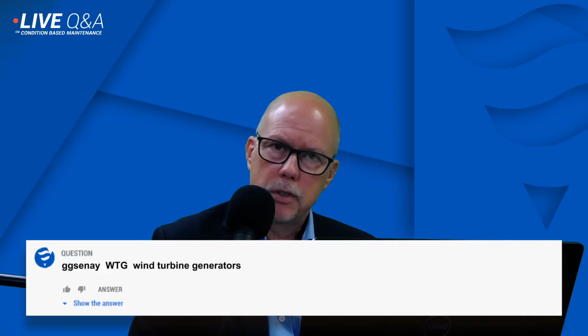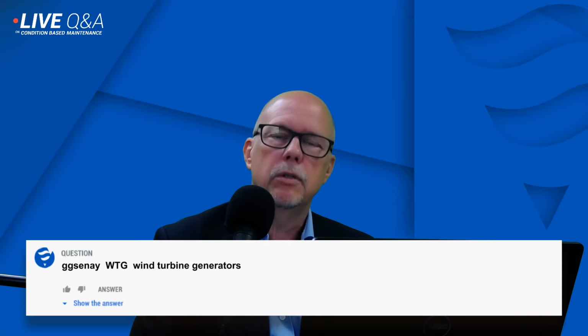But for windmills, if you look at a wind farm, there's quite a few units, and each of these units produces a small amount of power. So they don't generate a lot of money, and if one goes down, because the windmills, of course, if there's no wind, they're not working. If you have a windmill that goes down, it's not that much of an issue so far as we can tell to the utilities. But if we just look at the units per se, we do have equipment that could easily fit in those units and could provide critical information: air gap information, relative vibration information, absolute vibration information, displacement, temperature, flux.